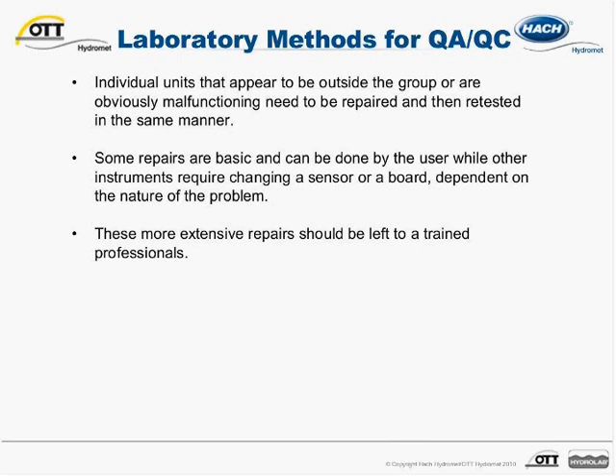Seeing data that does not fit the acceptance criteria or are obviously erratic should trigger further action. Check to see that everything with the sensor and setup looks normal and is performing properly. Consider recalibrating or performing the recommended maintenance routine.